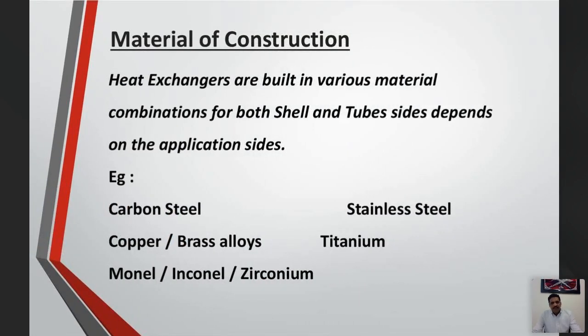Now we come to the material of construction. Heat exchangers are built in various material combinations for both shell and tube side, depending on the application side and how they want it. For example: carbon steel, stainless steel, copper or brass alloys, titanium, monel, inconel, zirconium, etc. There are so many materials available.